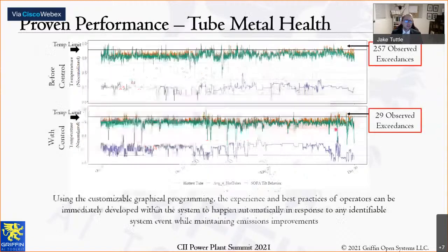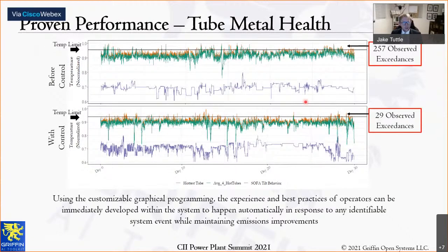Now, if we look at tube metal degradation inside of the system due to high metal temperatures, we see that before intelligent control was initiated, over the time span of about a month, there were 257 instances of high tube metal temperatures above this solid black line here. After advanced control, with a little bit more active control parameter down here in the purple, we see over an 80% decrease in the number of instances of high tube metal temperatures, representing greater tube life inside of the unit.